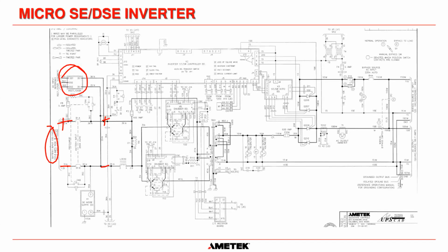But if you look, this positive comes in here and goes to the center tap of the transformer. So that is always positive. So that's just like the last page that we just looked at. And if you look at the negative coming in here, that goes to this point here, which is connected to the emitter of both of these sets of IGBTs. Now, it's slightly confusing here because we have 2 IGBTs in parallel, but that's basically how we increase the power of our systems. If we had 1 IGBT, it's probably going to do 5 to 10 kVA. 20 kVA would have 2 IGBTs in parallel, 30, maybe 3. As it goes up, we just put more and more IGBTs in parallel.